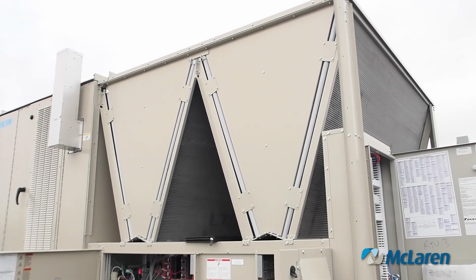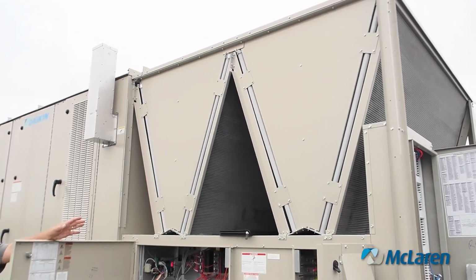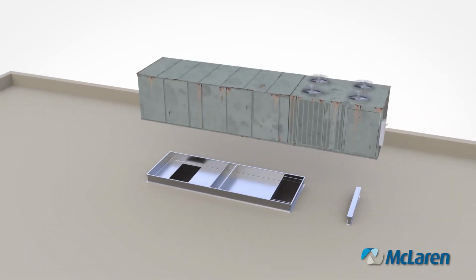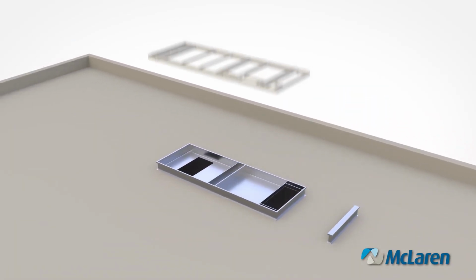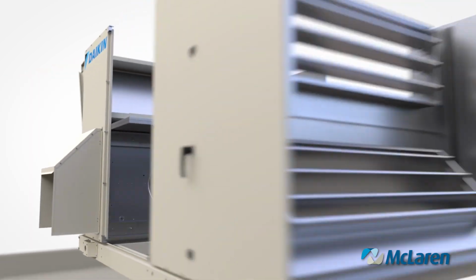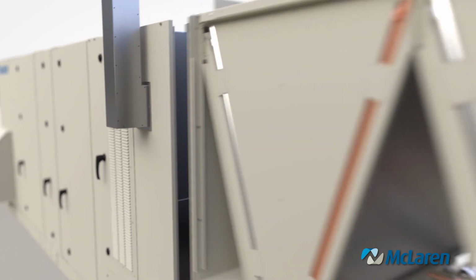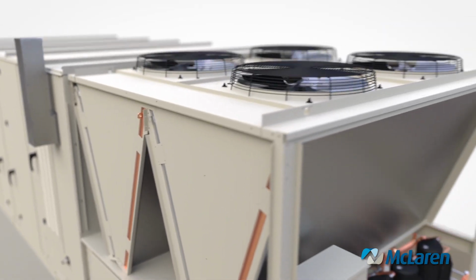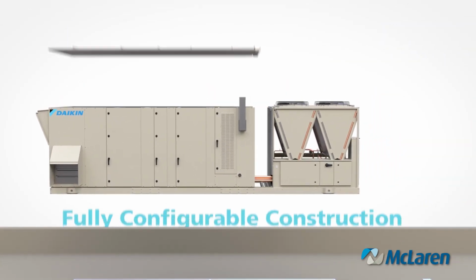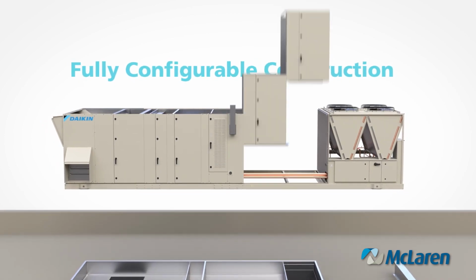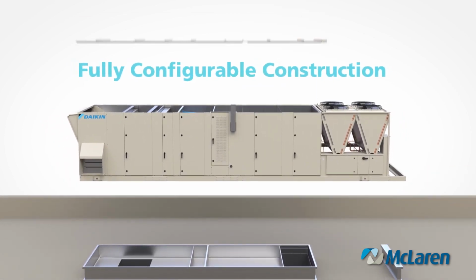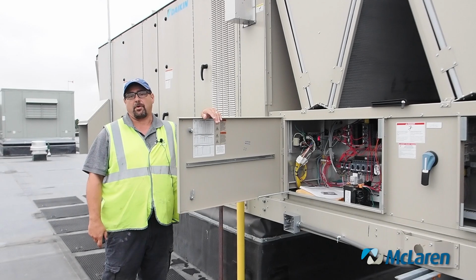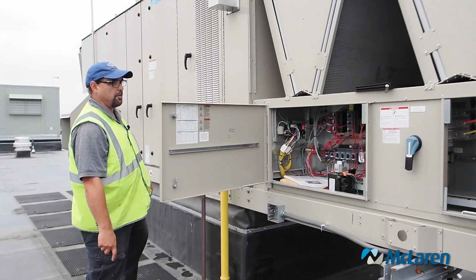That is a very thin coil. No pressure washer, no chemicals. When it gets dirty, the right way to clean it is from inside and out with the water. To do that, lock out, tag out your power, climb up on top, take off just the cover of the condenser fans and get a hose in there and clean them out. It's a lot easier than trying to take off one of these triangle pieces. I've tried both. Moving on to the next compartment.